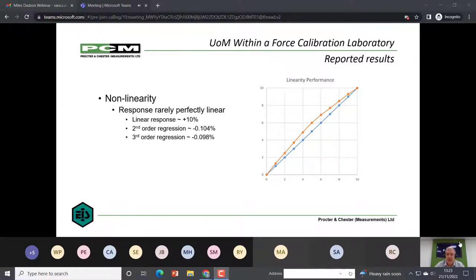However, if you carried out a linear evaluation of zero and full scale, the actual response of this device is 10% error at midpoint, which in any chart is a terrible device for that kind of performance. However, most calibrations for force measurement offer the second and sometimes even a third order regression. So for a second order regression, the actual error drops down to minus just over 0.1%, and a third order is just under minus 0.1%. Quite often when you're having regressions like this, you will have a regression which is force in terms of response, which a lot of instrumentation will allow you to put those regression coefficients into, and you actually take out this non-linearity almost entirely.